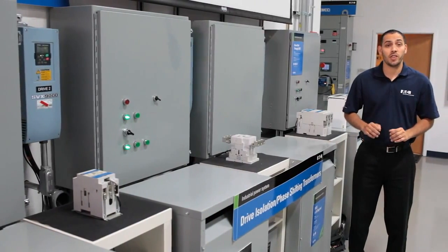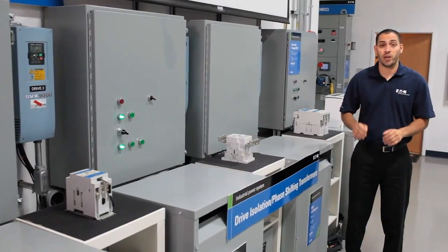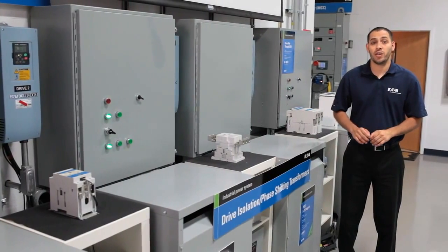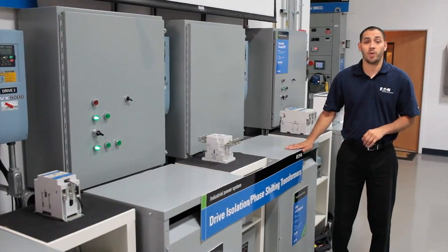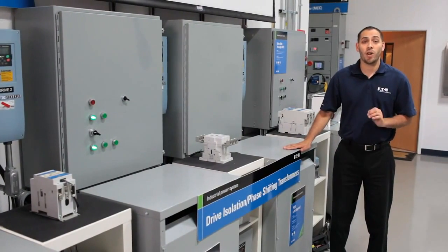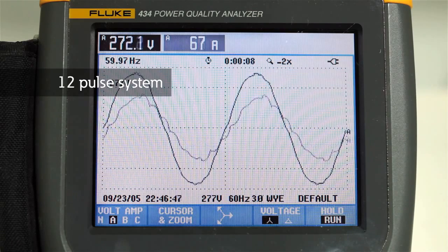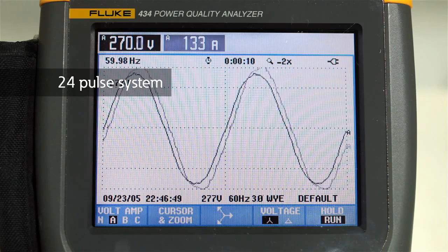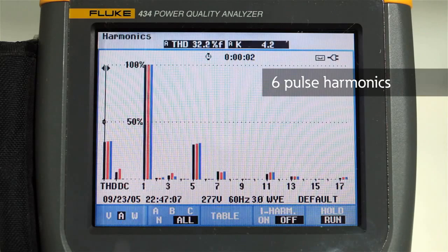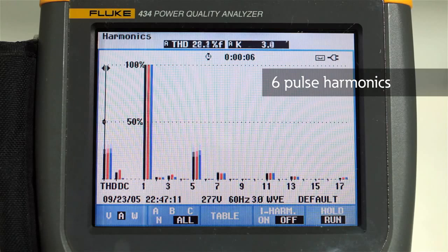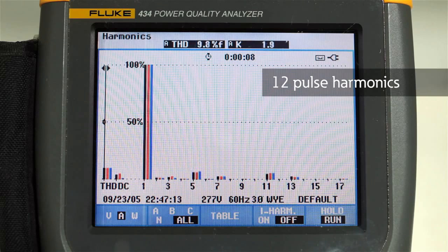Finally, a third solution is the use of special transformers. Harmonic mitigating transformers and phase-shifting transformers can be used to cancel the harmonic currents. For example, phase-shifting transformers can transition a system of 6-pulse drives to reduce the harmonic distortion in the current and voltage. These waveforms show the transition of a 6-pulse system to a 12-pulse system to a 24-pulse system.